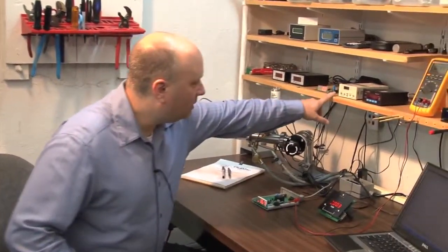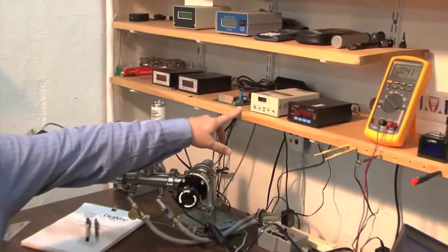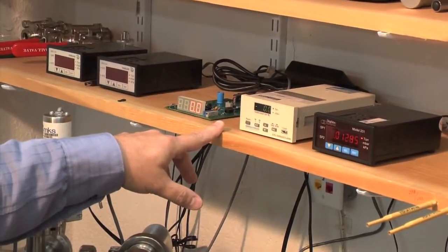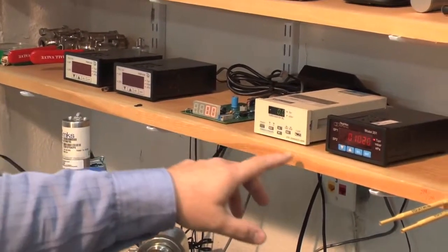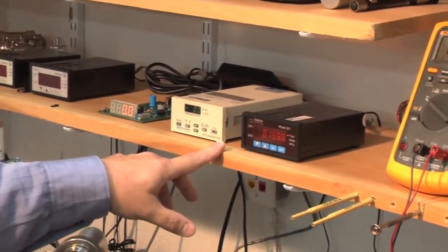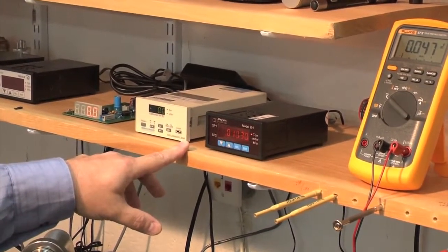Digivac maintains several standards which are NIST traceable. My Convectron gauge is an ultra-low vacuum gauge, good down to 10 to the negative third. We use this for readings between negative third and one torr. Our Baratron gauge is used for readings from one torr up to atmosphere, generally presumed to be about 760 torr on any given day.